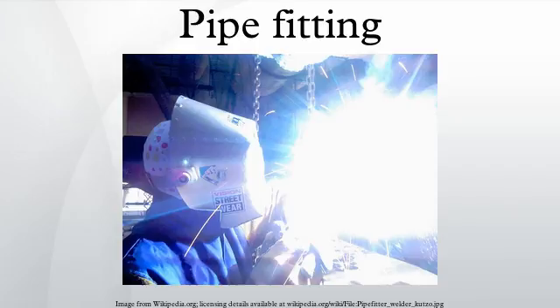Crimped-pressed connections. Crimped-pressed connections use special copper fittings which are permanently attached to rigid copper tubing with a powered crimper. The special fittings, manufactured with sealant already inside, slide over the tubing to be connected. Thousands of pounds force per square inch of pressure are used to deform the fitting and compress the sealant against the inner copper tubing, creating a watertight seal.